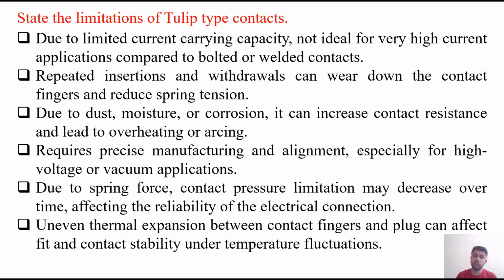The limitations of tulip type contacts. There are several disadvantages of this type of contact. Some are listed here and we are going to discuss them right now. Due to limited current carrying capacity, it is not ideal for very high current applications compared to welded contacts. Repeated insertions and withdrawals can wear down the contact fingers and reduce their spring tension. Due to dust, moisture or corrosion, contact resistance can increase and lead to overheating or arcing.